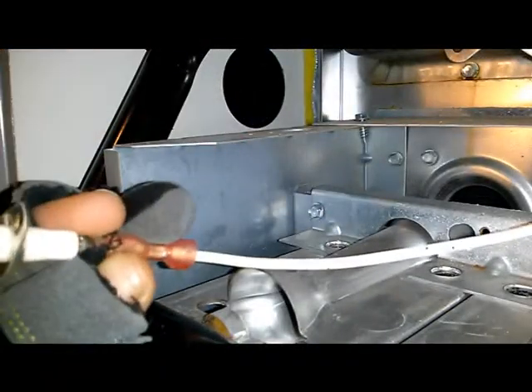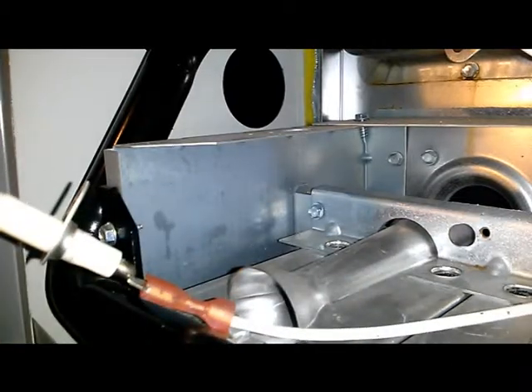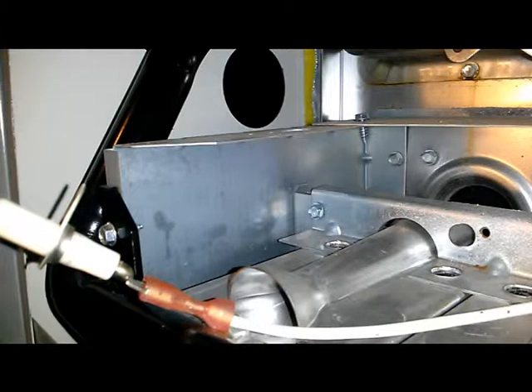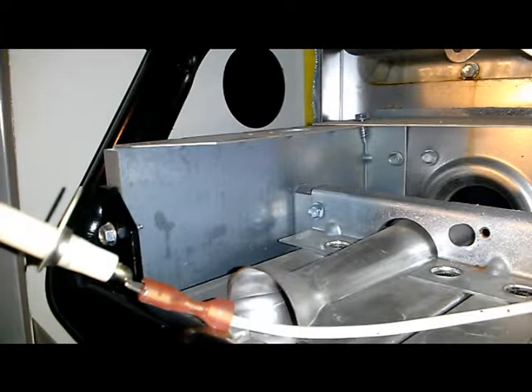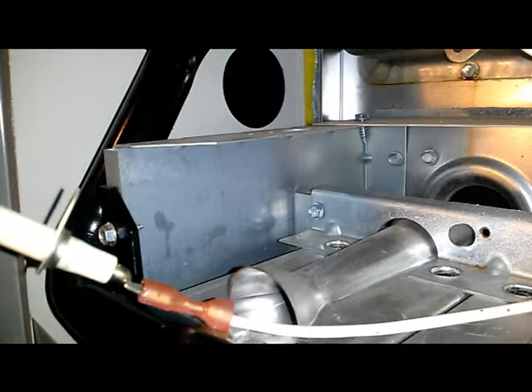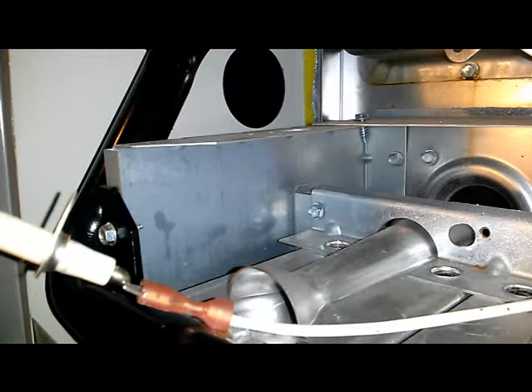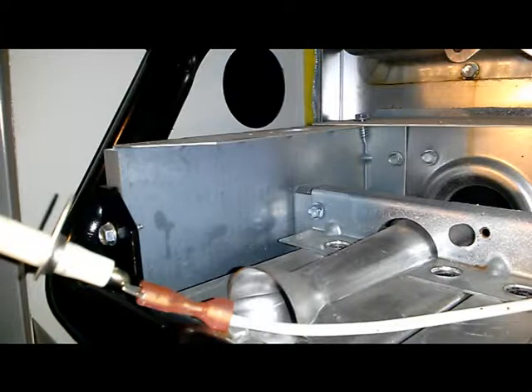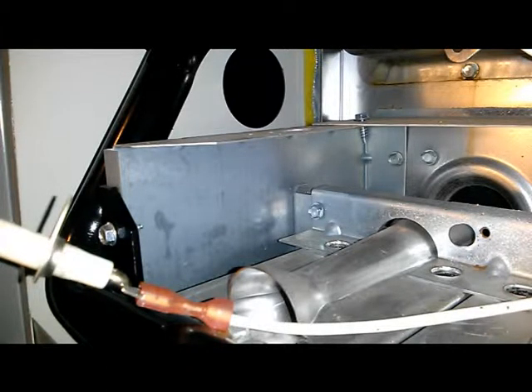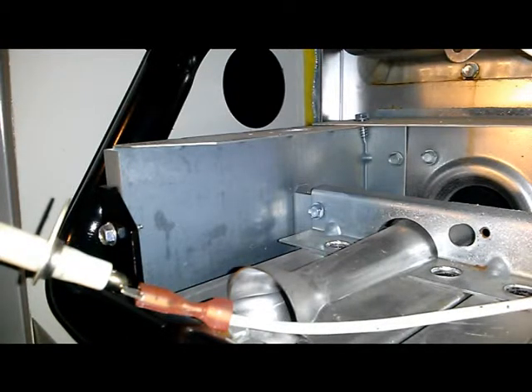These guys can be a pain for you, the homeowner, because they're not anything spectacular, and if they're not cleaned, they'll turn your furnace off. You'll think there's a bigger problem than there actually is. Your furnace will come on, then turn itself off, relight itself, and might stay on, and you'll be thinking, okay, what's going on here? Over time, if you let it continue, eventually it's just going to not come on at all, or it'll lock itself out, because this flame sensor, this flame rod, is dirty. That's it. That's the only reason why your furnace is acting the way it is.